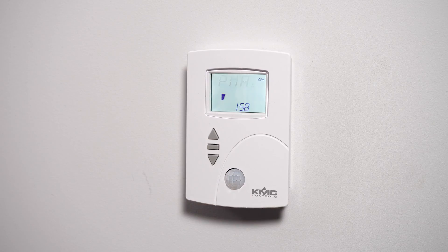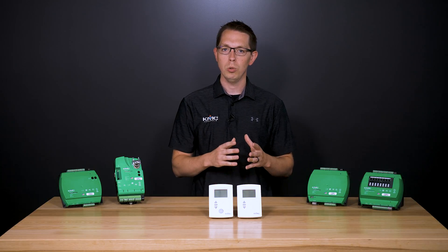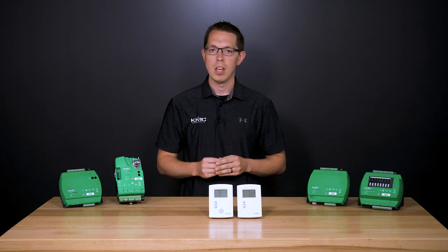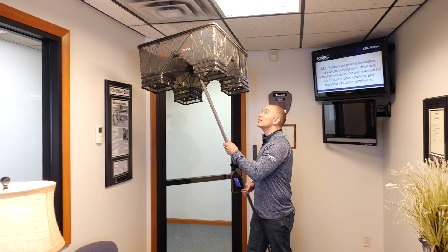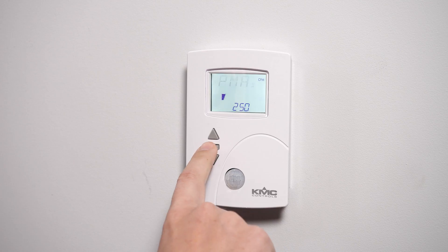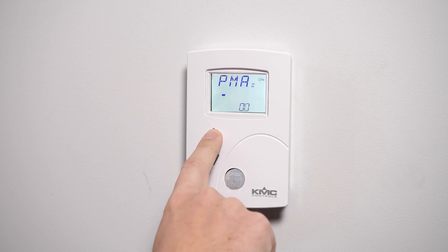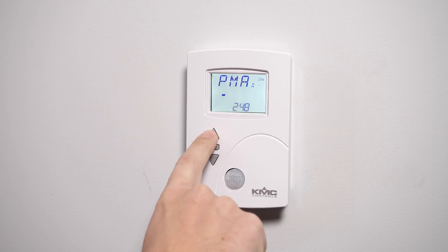Now it's time to measure and enter the maximum primary airflow. The display will begin flashing Pmax and shows the uncorrected airflow. The airflow will attempt to stabilize on the highest value for either the cooling or heating maximum airflow. Wait for the maximum airflow value on the NetSensor to stabilize. With a flow hood, measure the actual airflow. Press the enter button to advance to the entry display — the Pmax display will stop flashing. Press the up or down button to enter the measured airflow and press enter to save it.